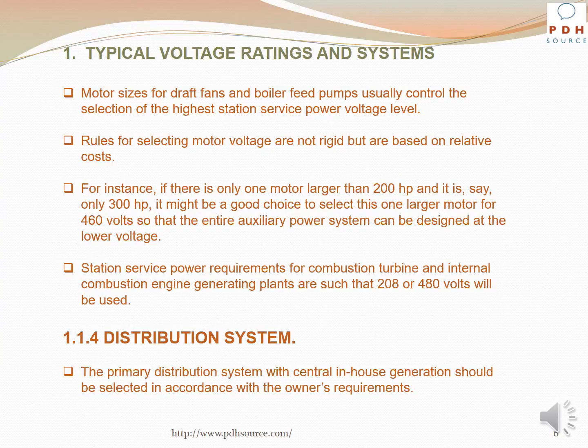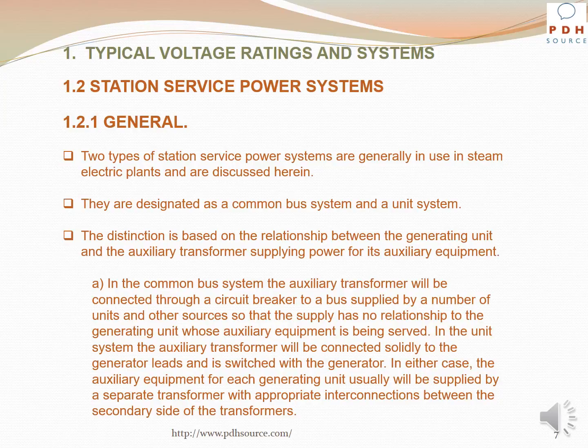Station service power requirements for combustion turbine and internal combustion engine generating plants are such that 208 or 480 volts will be used. The primary distribution system with central in-house generation should be selected in accordance with the owner's requirements. Two types of station service power systems are generally in use in steam electric plants and are discussed here. They are designated as a common bus system and a unit system.